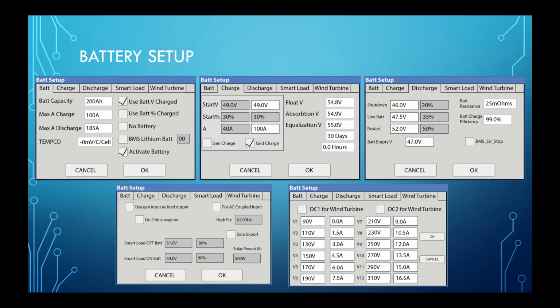The voltage and percentage mode, I would like to point out, is dependent on which one you're using beforehand. In the previous tab, the BAT tab, you have use battery percent charge and use battery V charged. In most cases, if you're in lithium mode, it will be in percent mode. It's pretty straightforward because we are getting that information. But everything throughout the settings is very dependent. If you do not have comms, voltage mode is the only thing that you'll be setting if that's selected. Percent, same thing. Discharge tab, again, very important to set appropriately for the batteries.